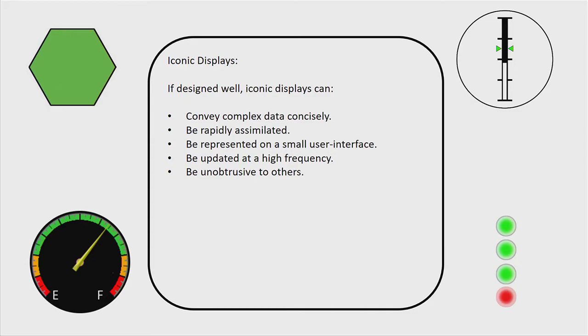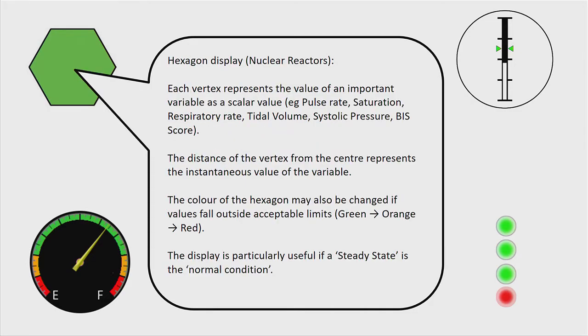The first icon is borrowed from the nuclear power industry and is called the hexagon display. It puts a scalar value on each vertex of the hexagon, and as the value changes, the vertex moves and the hexagon changes shape — it may also change colour. In practice it doesn't work very well during anesthesia because things are changing too quickly, but it works quite well on bypass and is a very good indicator of the steady state.